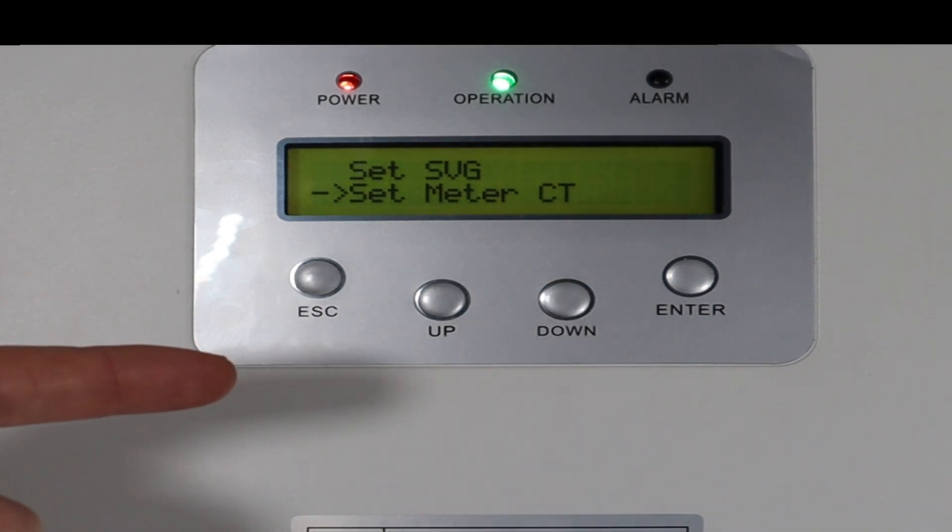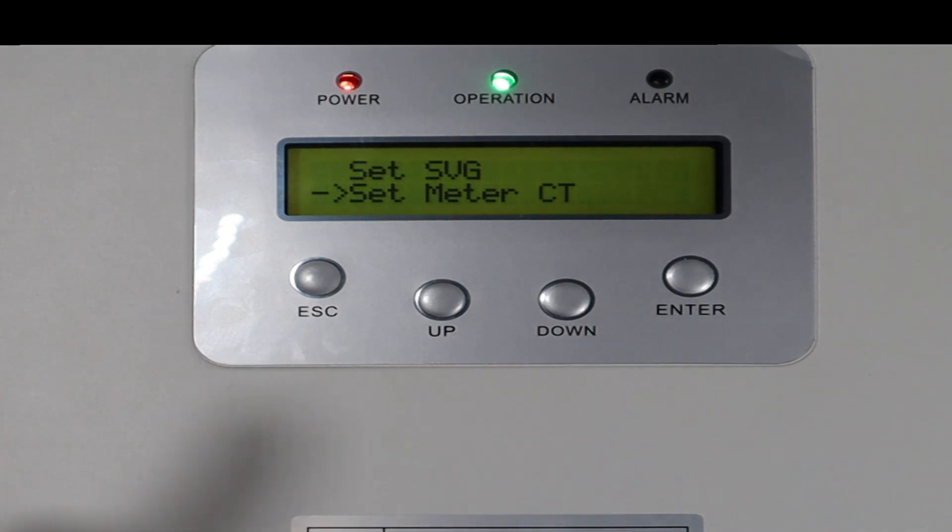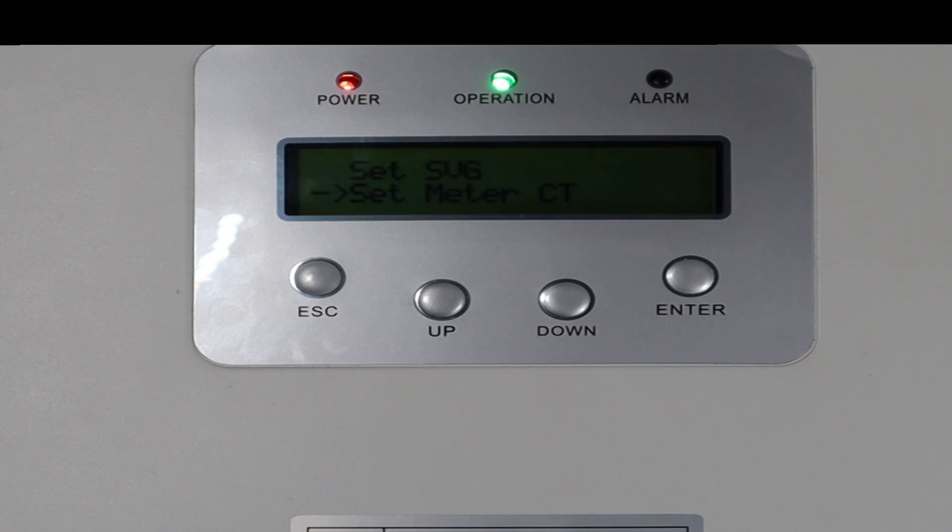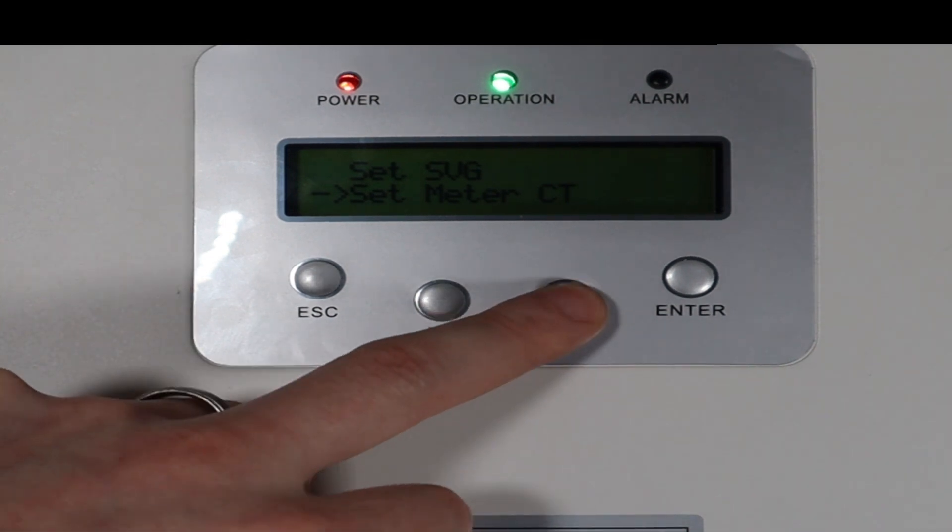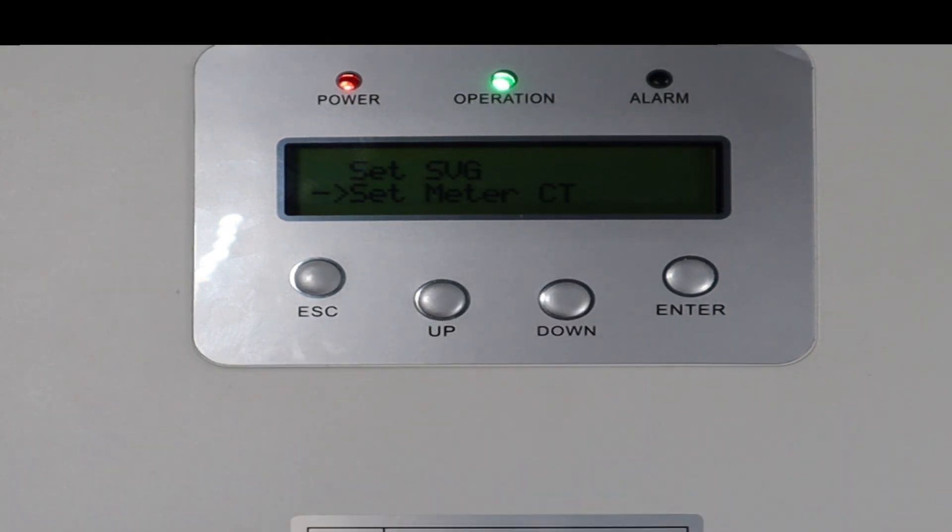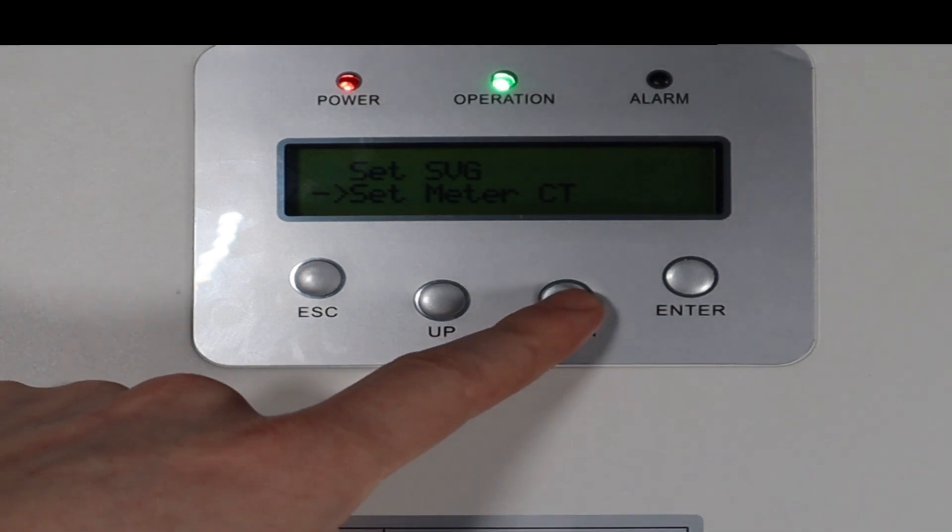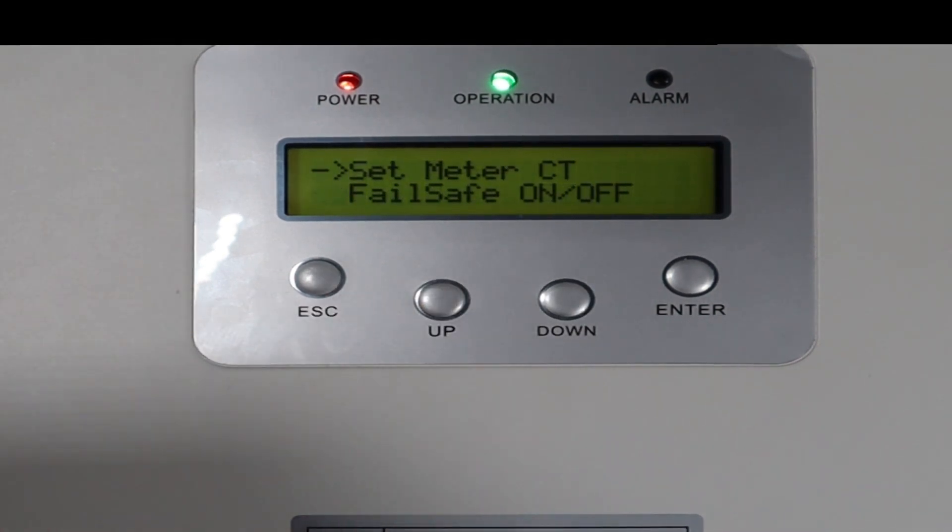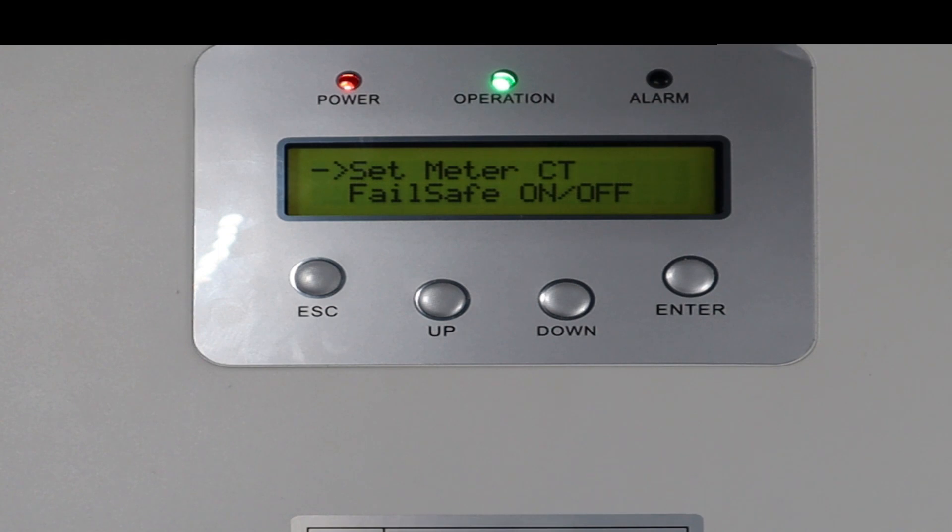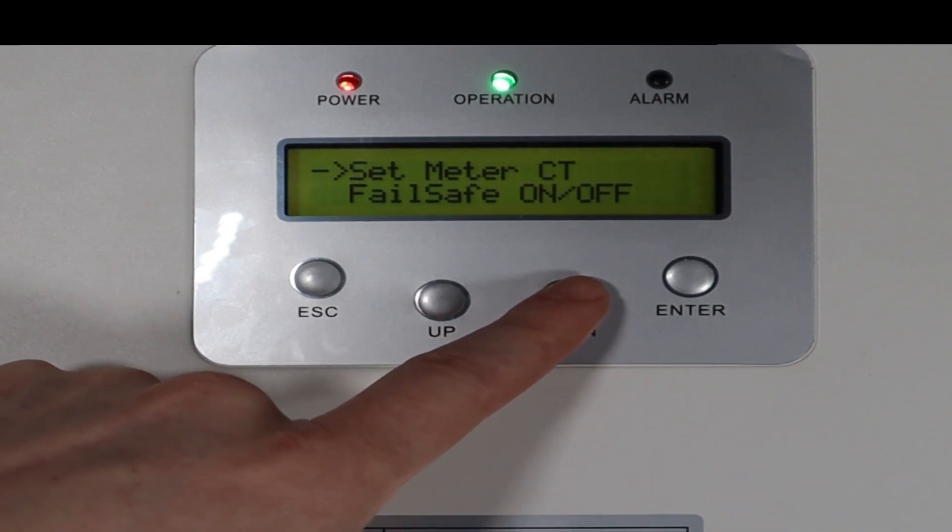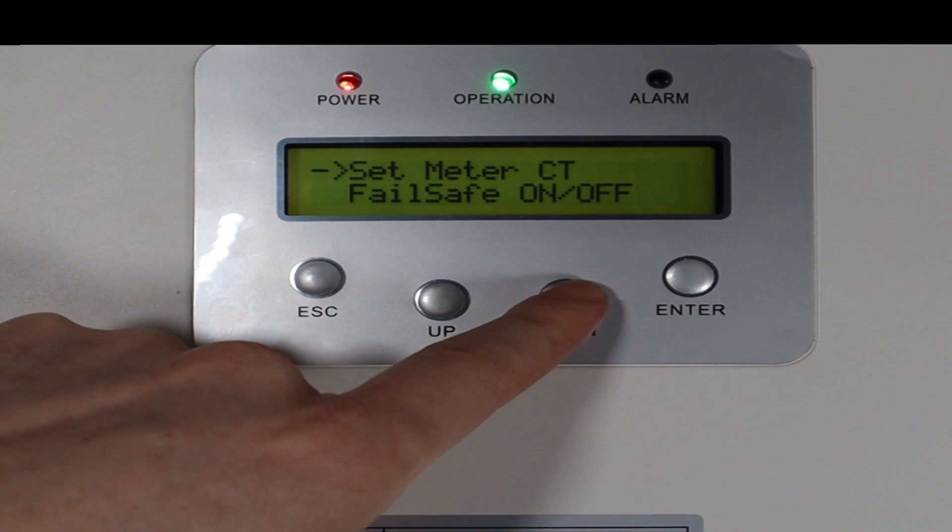And if you don't know the CT ratio of your CTs, you can actually, all the CTs that I've ever seen, actually have it printed on the physical CTs. So you should be able to get it from the CTs themselves, if you can't speak to the system designer who purchased them. What's very important for purchasing CTs for this EPM is the primary must be greater than the maximum current that ever went through the system. So if you don't know the maximum current that will ever go through the system, the best way to look for that is look at the mains transformer. It will have a silver plate and it will tell you the maximum current. Or look at the circuit breaker, the main circuit breaker, it will have a certain current writing on it. And it'll tell you the maximum current that will ever run through that cable. The primary for that CT must exceed that. So if you've got 1000 amp transformer, your CTs must be 1000 or higher. So 1000, 1200, 1500. Don't go too high, but you can go a little bit higher. The higher you go, the less accurate it is. Then the secondary current needs to be 5 or 1. So the more accurate is 5, but we've tested under G100 up to 1 amp on the secondary. So both will work. But going down to 33 milliamps, you need to be careful.